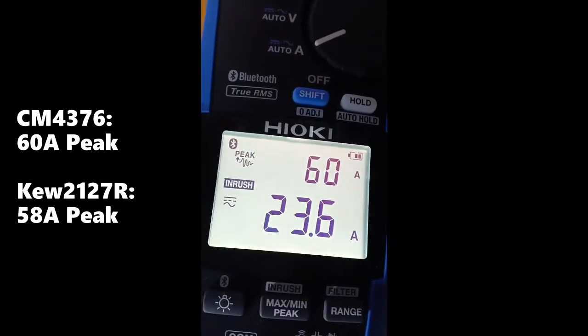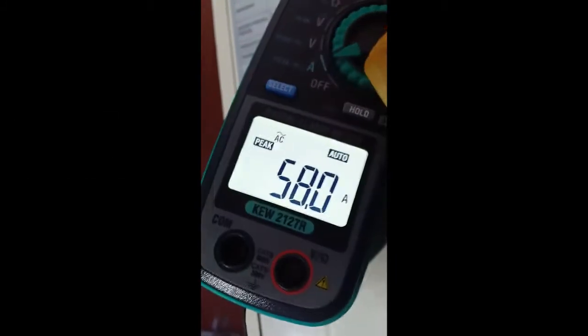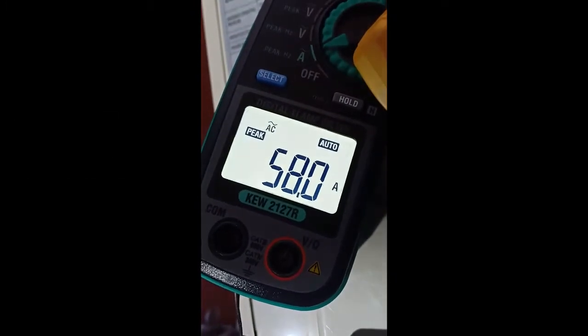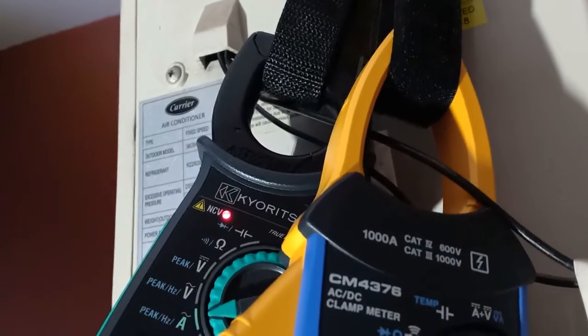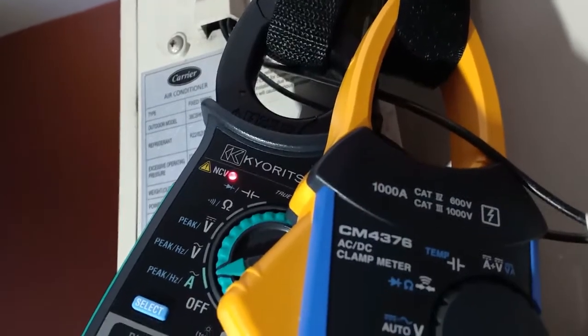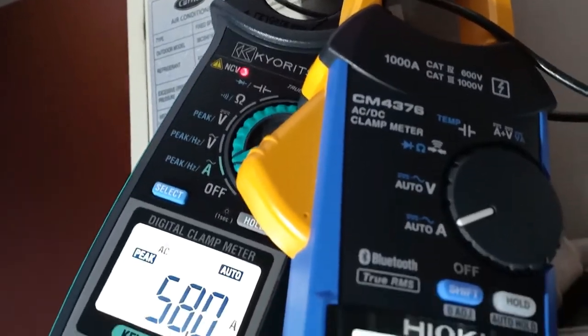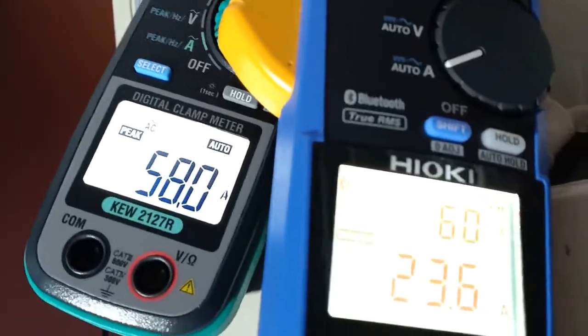The peak value for the inrush current for the KEW 2127R was slightly lower by about 2 amperes from the value displayed by the Hioki CM4376. This is acceptable — it was consistent and close enough.